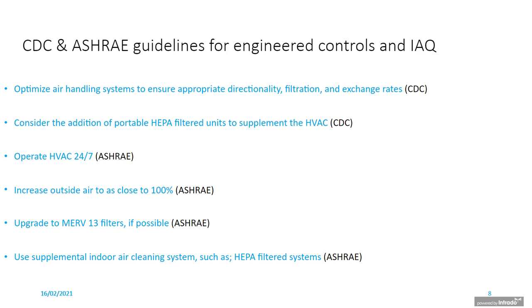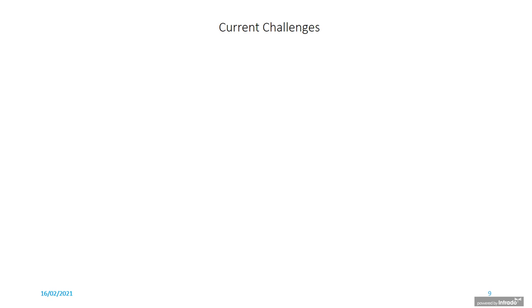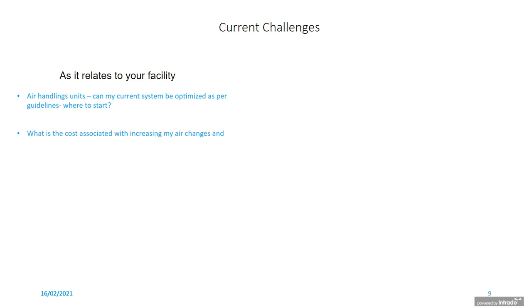And again, ASHRAE also wants to use supplemental indoor cleaning systems such as HEPA filtered systems as well. There's a lot of impact involved in all of these recommendations. As it relates to your facility, air handling units, how can you optimize it per the guidelines, and where do you start? It's very challenging. What is the cost associated with increasing my air changes and increasing my outside air? And what is the added cost to my heating and cooling loads? Also, what is the impact as it relates to relative humidity? All this is impacted as we increase air changes and add upgrades to filtered systems. We have additional pressure drops on the unit itself, so we have higher load factors.